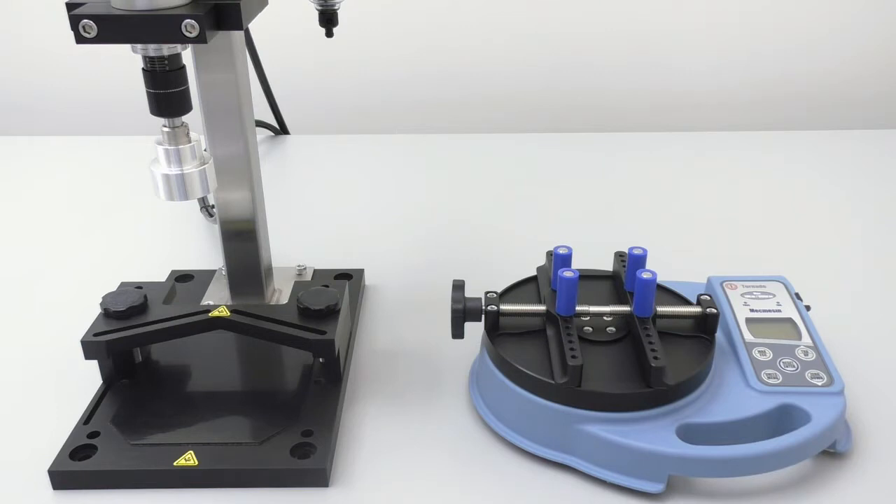In this video, we are going to use a Mecmesin bottle cap torque tester to calibrate a Kinex SA2000 capping machine.